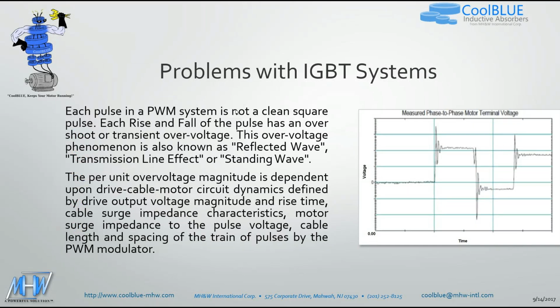In a VFD system, each pulse is not a clean square wave, as you see in the picture. Each rise and fall time of the pulse has an overshoot or a transient overvoltage. This overvoltage phenomenon is also known as reflected wave, transmission line effects, or standing wave. The per unit overvoltage magnitude is dependent upon drive cable, motor circuit dynamics defined by drive output voltage magnitude and rise time, cable surge impedance characteristics, motor surge impedance to the pulse voltage, cable length, and spacing of the train of pulses by the PWM modulator. So basically, it's a phenomenon that happens. It can't really be predicted as far as how bad it is, but it does. The VFD does basically create these overshoots, and the solution is to try to reduce and eliminate them as best we can.